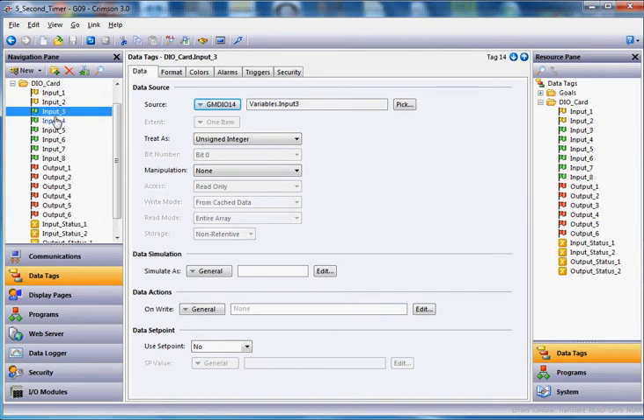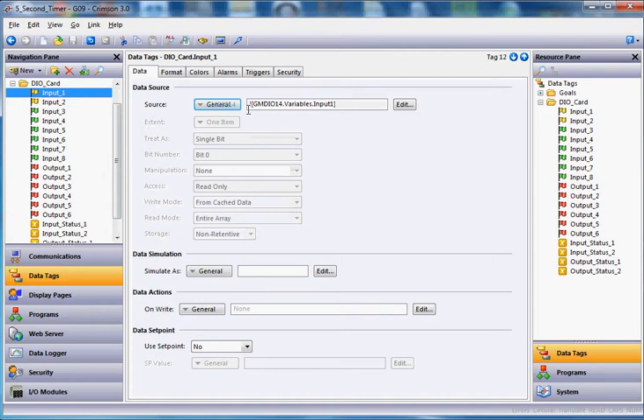The reason for that is these all come in as active high, and they're sinking inputs, so if you tie them to ground, that's when they go off. And so what I've done is I've added an exclamation point right here in front of it, which NOTs that so that the logic will correspond correctly to how we're thinking.